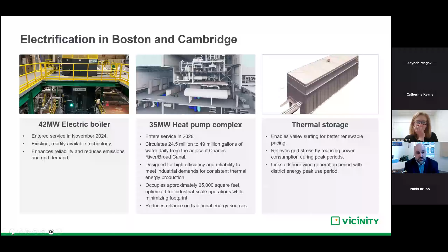The last technology we're putting in place is thermal storage. Just like the first two, where we do things at city scale, our thermal storage system is going to be rather large - we're looking at 600 to 1,000 megawatts of thermal storage capability. One of the great things about thermal storage is it's not particularly complex, and it doesn't take up a very large footprint. At our existing Kendall Station plant right in downtown Cambridge, we can actually install up to 1,000 megawatt hours of thermal storage. Oftentimes you don't see thermal storage because the end product many of us need is electricity, but if the end product you need is heat, you can deploy thermal storage technologies that are relatively low cost, not expensive, and don't take up a very large footprint.